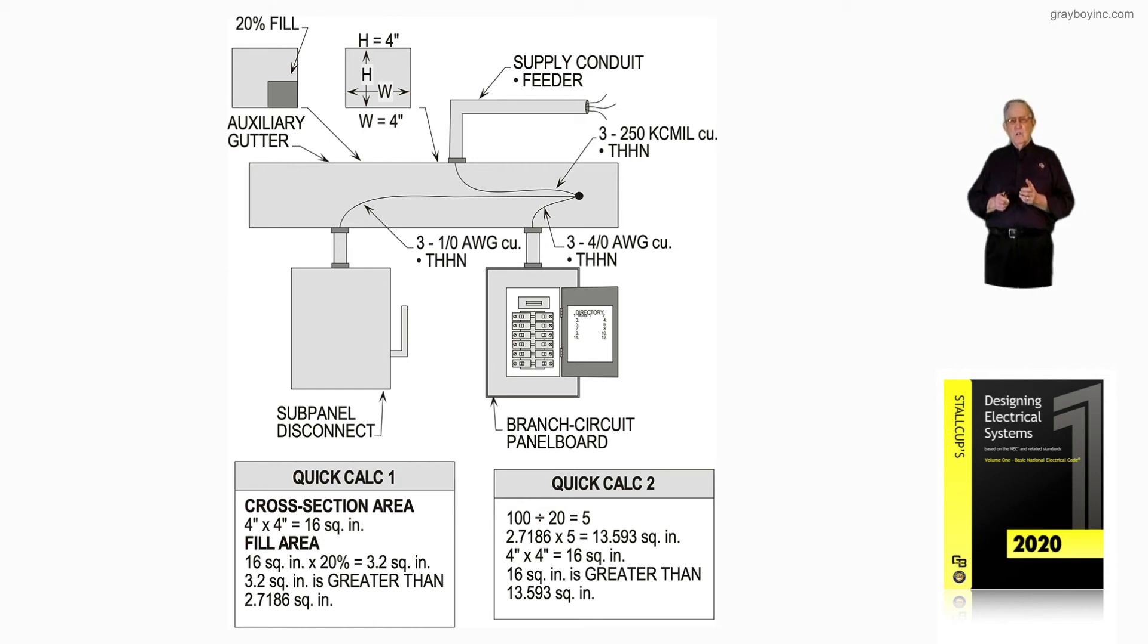Quick calc 2 says if you don't want to use the method of quick calc 1, then just take the 20% fill, divide it into 100, and get the reciprocal of 20, which would be 5. Then take the cross-sectional area of all your conductors coming into it, and that would be 5 times 2.7186, and that would give you a square inch area of 13.593. A 4x4 gutter at 16 square inches is greater than 13.593, so a 4x4 gutter could be used.